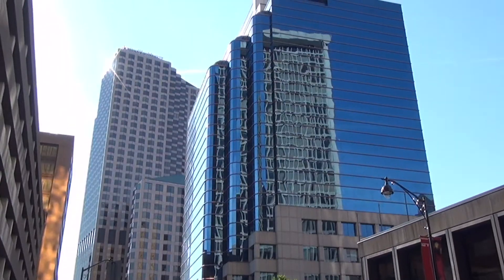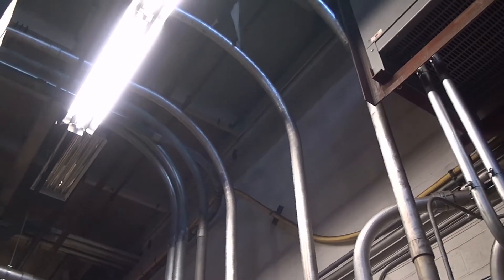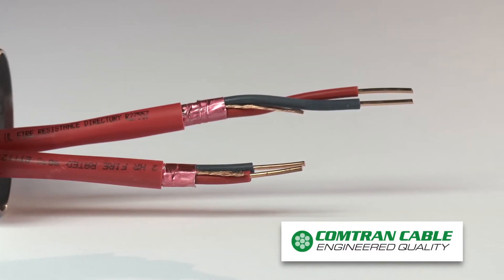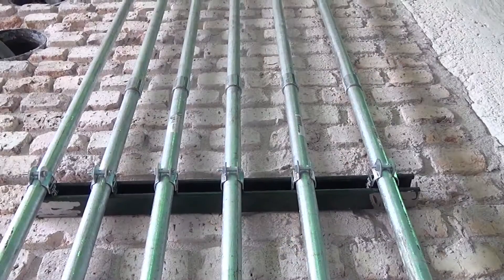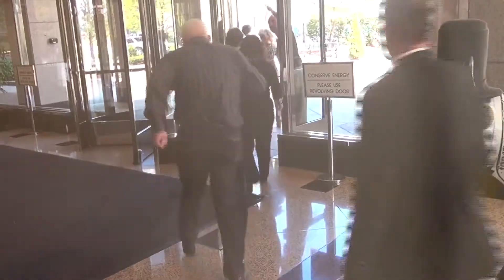Vertical distribution, especially in high-rise buildings, requires a large number of cables in close proximity that not only have a higher probability of failure in the event of a fire — they also have the potential to spread fire to the entire structure. In the testing furnace, standard ETP copper conductors fail within 20 minutes in 8 feet of conduit, while VitaLink lasts 2 hours in the same conditions. Other manufacturers cannot make these claims. Test results provide clear evidence that VitaLink fire-rated cables perform far beyond the minimum requirements.